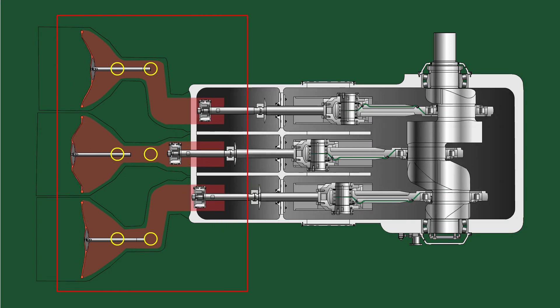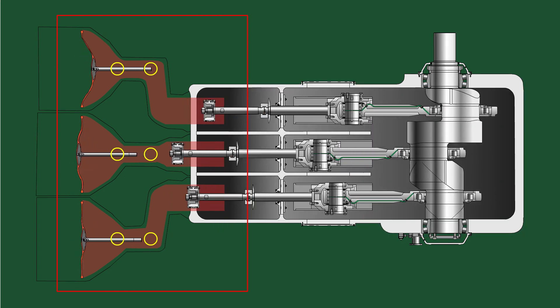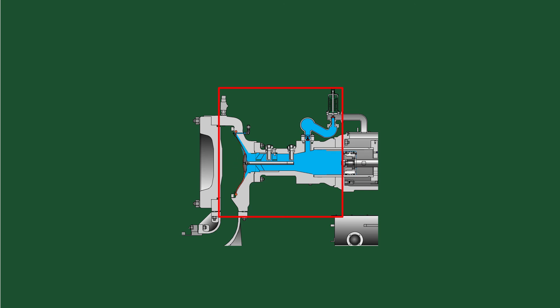Continue the manual cranking until no switch lights light up during rotation of the pump. This indicates that all chambers are filled properly with propelling liquid and the monitoring rod indicator is moving properly between switch ZSL and ZSH, thus reaching the correct position of the diaphragm in relation to the piston position.